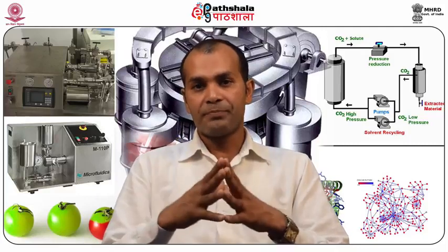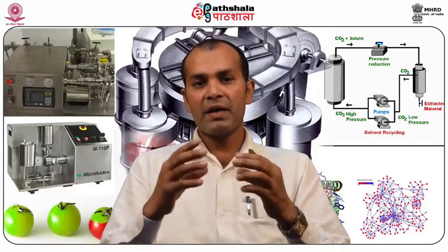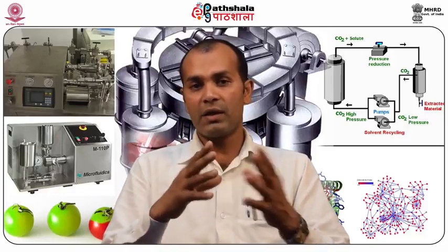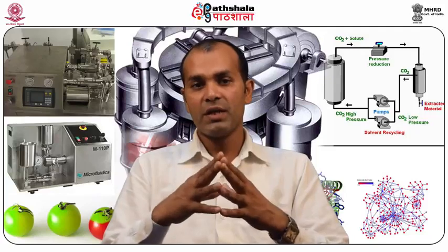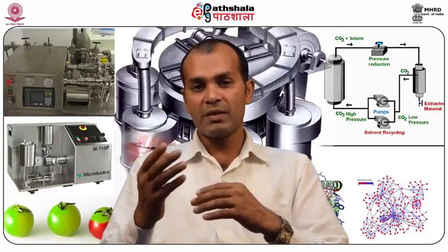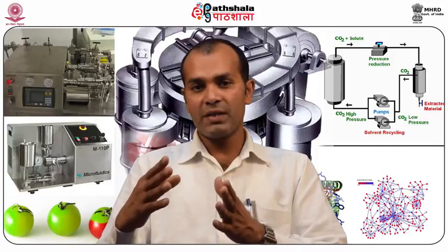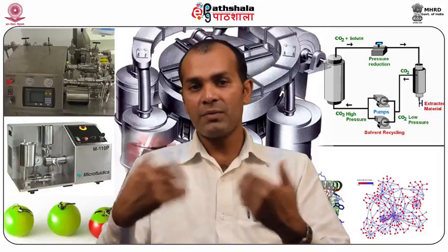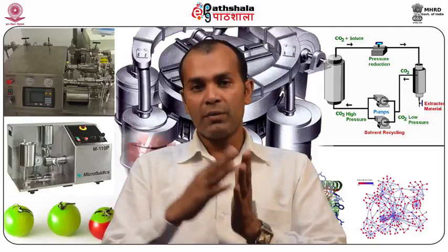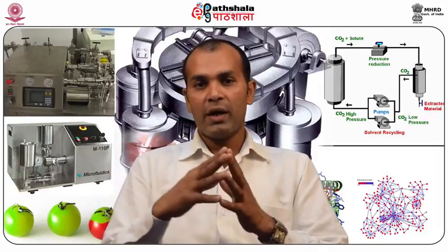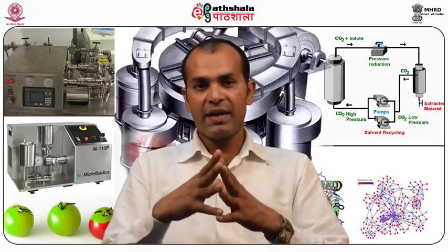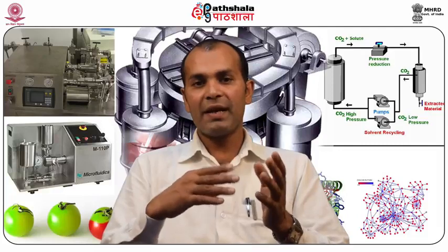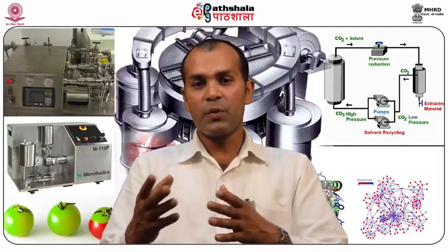Their integrity and ever-increasing stability toward pH: as we know, till now there are 3 or 4 membrane generations. Their sensitivity toward pH in the first generation is such that only a 3 to 8 pH range is applicable. In the second generation it is wider, and then the third generation, where the mineral membrane comes into the picture, we can operate in the full pH range 0 to 14. Pressure, temperature and environmental factors make them highly suitable for multi-purpose application in an array of industrial products.